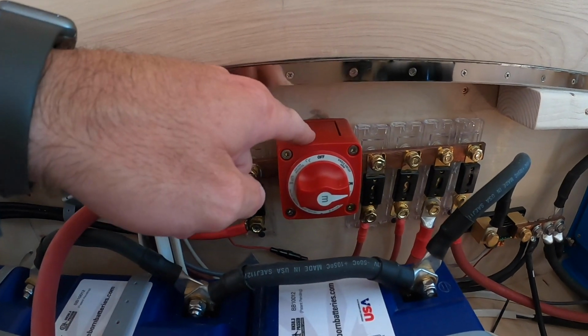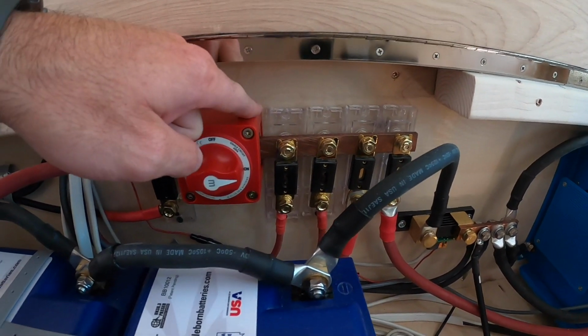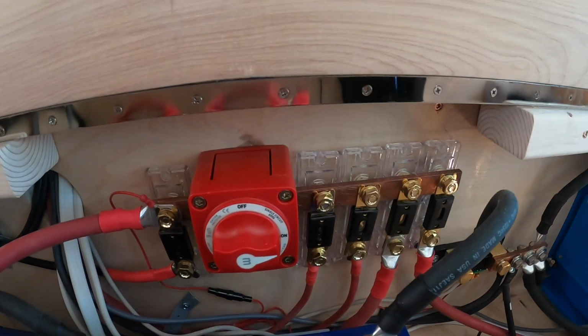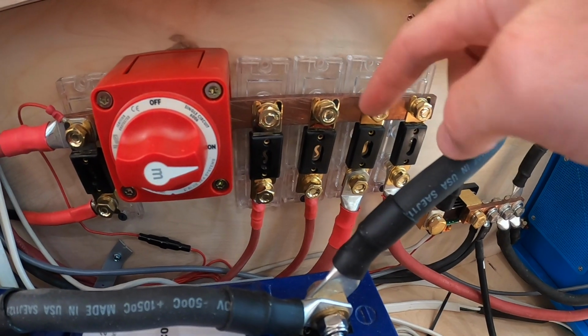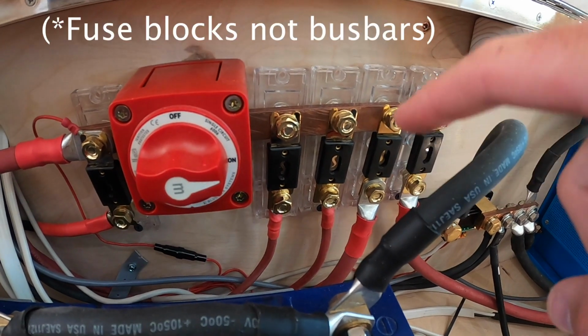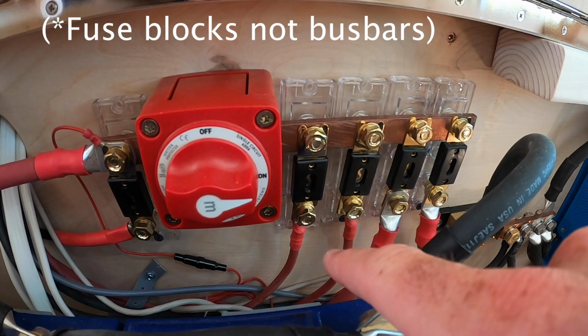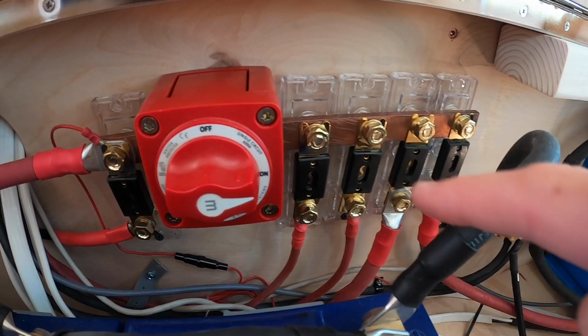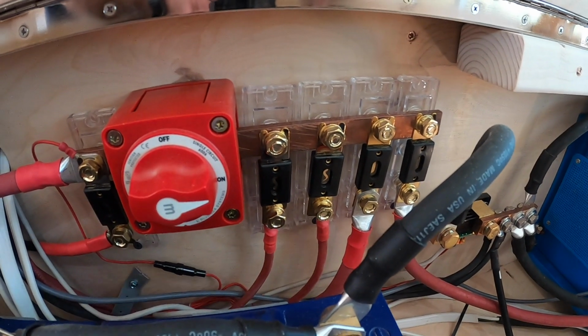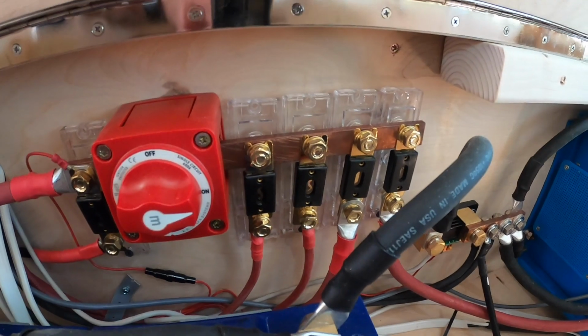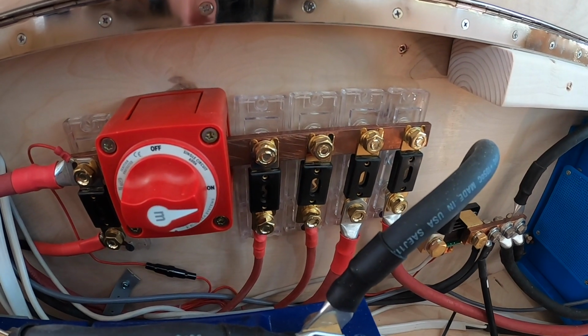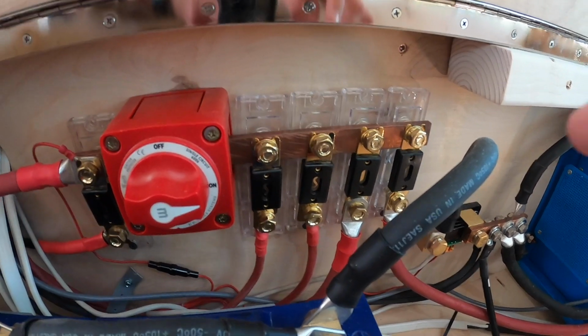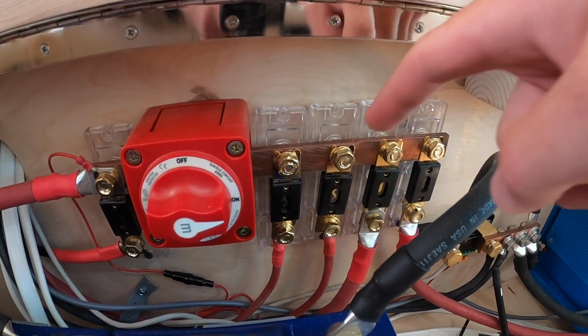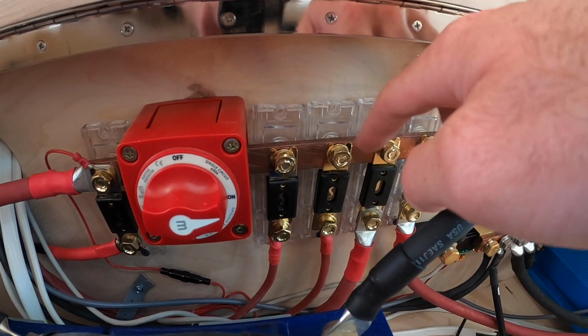From the kill switch, we go into our positive bus bar, and we have 4 connections. The first 2 are for our DC bus bars, using 6 gauge wire below, and I believe these are 100 amp fuses each, since our DC fuse panel is 100 amps each. We have 2 of these, one for each fuse block.